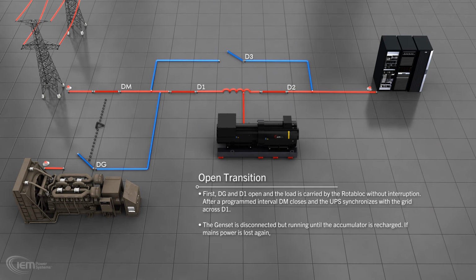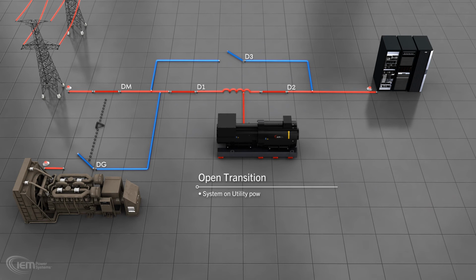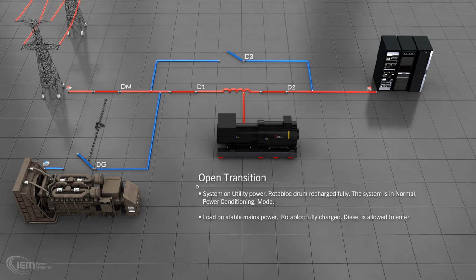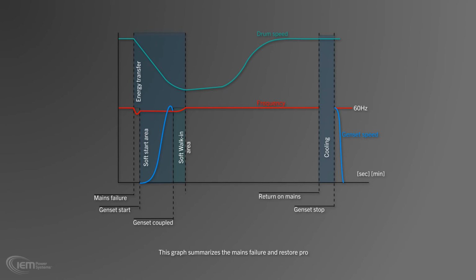If mains power was lost again at this stage, the load can be quickly and seamlessly transferred back to the genset. Once the system has returned to utility power and the drum is recharged fully, the system is in normal power conditioning mode. With the mains restored and the Rotabloc fully charged, the diesel is allowed to enter cool-down mode. This graph summarizes the mains failure and restore process.